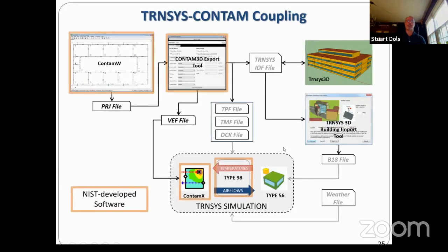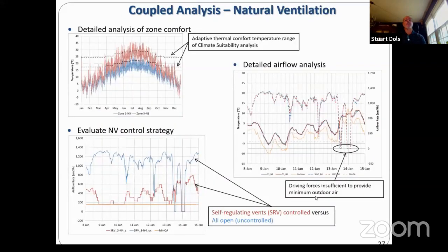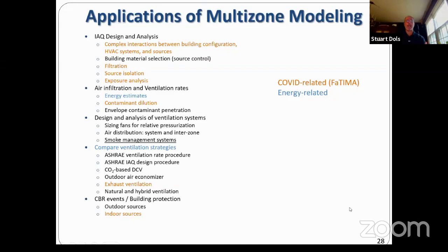The same has been done with TRNSYS, a very similar process. Now we can look at coupled analysis — for instance, demand control ventilation — and compare performance of the system under a leaky building envelope versus a tight building envelope, since leakage can confound system performance. We can evaluate energy saving measures and their effect on indoor air quality, and look at how energy saving measures affect non-controlled contaminants. We can do natural ventilation analysis, look at different control strategies with self-regulating or uncontrolled vents, and identify where driving forces are insufficient to provide outdoor air — perhaps requiring a hybrid system.